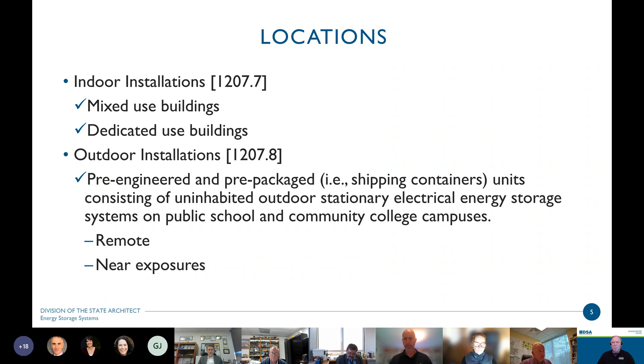Per 1207.8 of the fire code, these are broken out again into either remote locations or those deemed as near exposures. Given many of our campuses and the congestion they already see by size, I anticipate it will be the near exposure requirements that most designers will be dealing with. Again, there's a picture of some indoor and outdoor prepackaged units. Generally, the outdoor ones are going to be in converted ISO shipping containers.